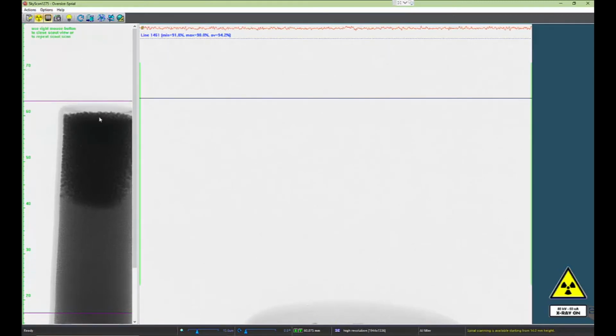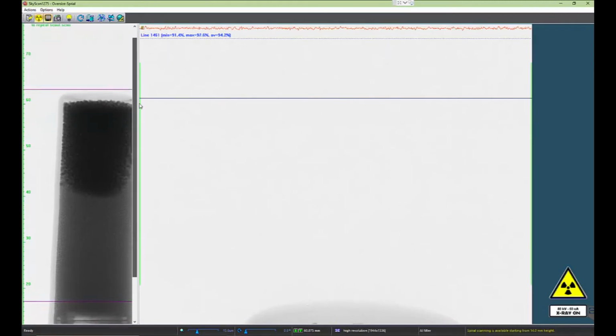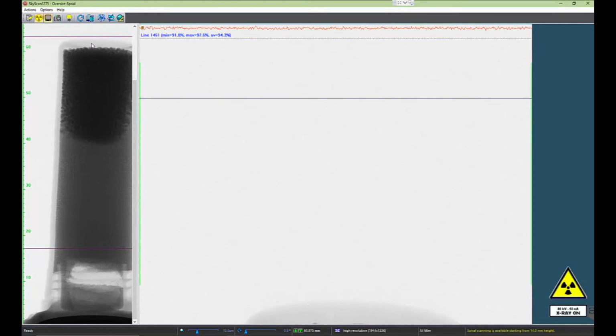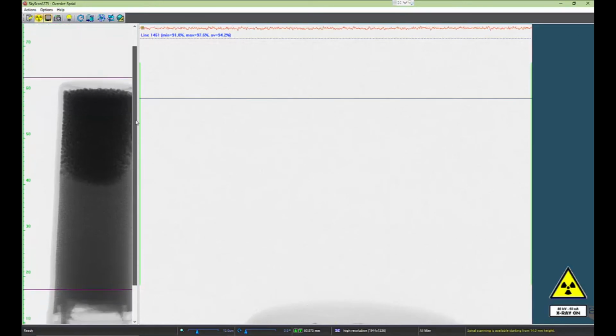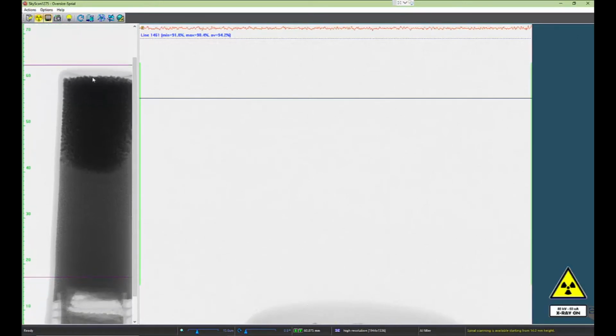So that's our traditional oversized scan, and now we can also see the bounds of our oversized spiral scan and understand what percentage of the sample can be captured under that setting. So say I want to capture these larger beads using a spiral scan.